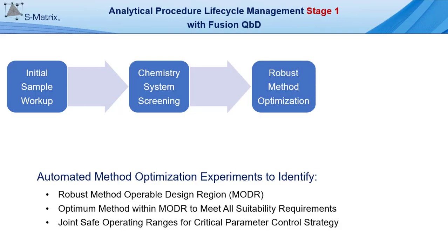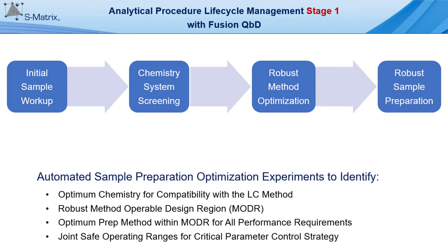This takes us through robust method optimization, where Fusion QBD enables you to identify the robust method operable design region (MODR), the optimum method within the MODR which meets all system suitability performance requirements, and the joint safe operating ranges for the critical parameters which can be transferred to a control strategy. In addition, Fusion QBD supports robust sample preparation method development, enabling identification of the optimum chemistry for LC method compatibility, the MODR of the sample preparation method, the optimum prep method within the MODR, and the joint safe operating ranges for critical parameters that can be transferred into a critical parameter control strategy.